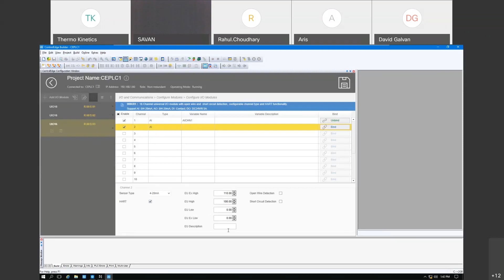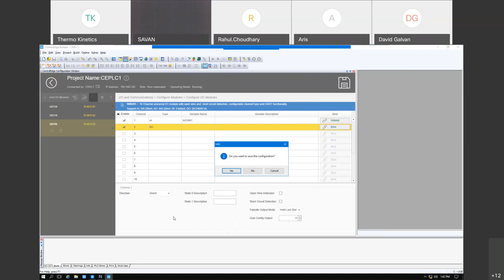Sensor type, it's a 4 to 20. I want to enable HART. I do have a HART transmitter connected to the other end of the wire, and then you would give it a description here with your ranges. If I want, for instance, an AO, same thing. You want 4 to 20, 0 to 20. Then my DI or DO. That's where you do that. I'm not going to save that.